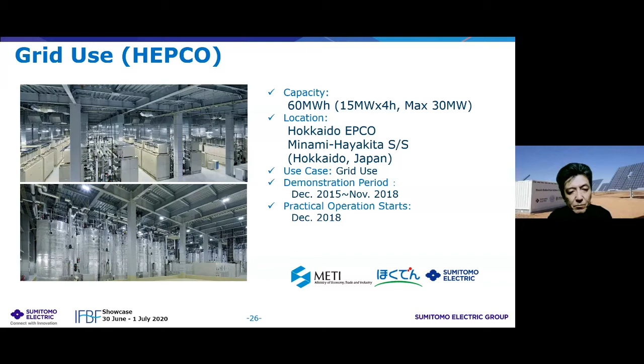Using this system, the battery itself and various control methods were evaluated. I'll show representative data. As for control method evaluation, high-speed response was evaluated, testing followability to a very fast command. The graph on the upper left is an example of governor-free operation, with the upper picture showing grid frequency and the lower picture showing battery output.